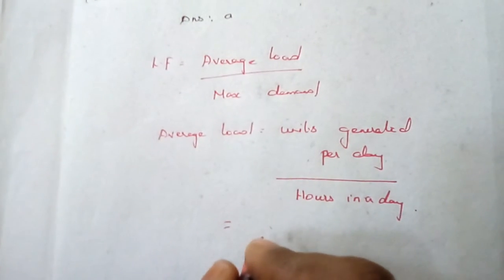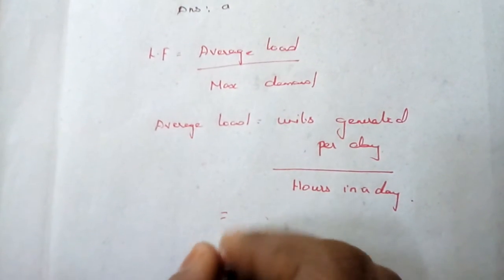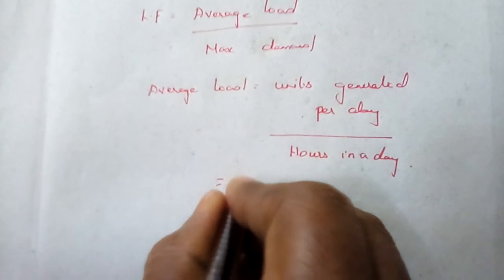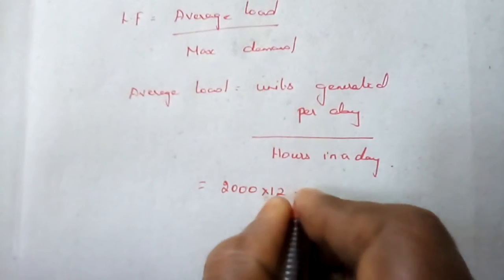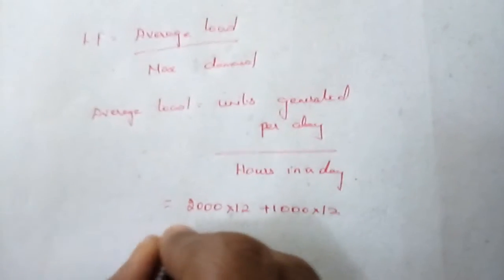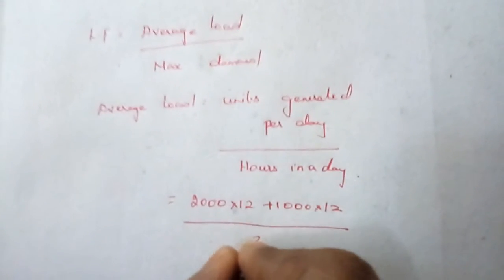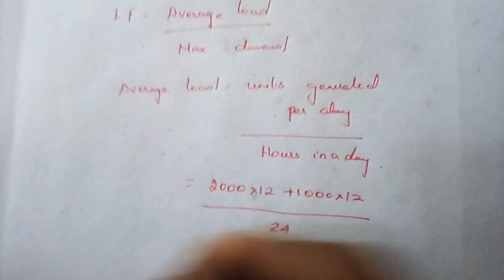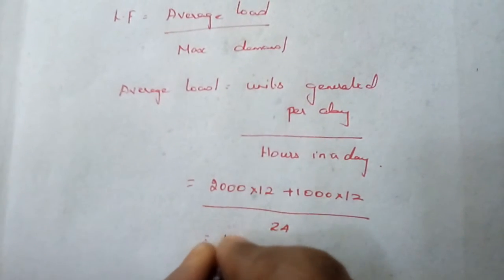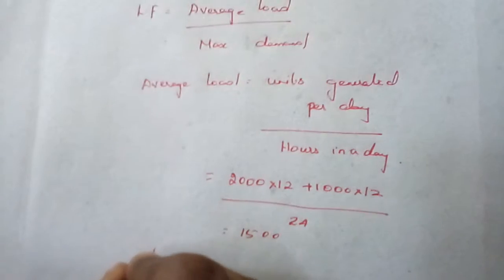Let us find out the average load first. The average units generated per day is given by: 2000 into 12 plus 1000 into 12, divided by the total hours which is 24. By this we get the answer of 1500 kilowatt.